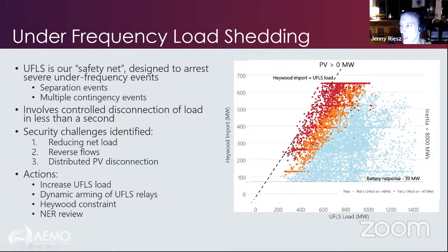What we've found is that because the rooftop PV is installed on the same circuits as the load, and those relays sit in the distribution network, that PV is eating away the load on those circuits. And when the relay trips, it detects the severe under-frequency and trips off that load. There's much less load there now, so it has much less effect in terms of arresting a frequency decline. And when it goes into reverse flows, where there's so much PV on that circuit that it's actually pushing energy back into the grid, the relay doesn't know that.